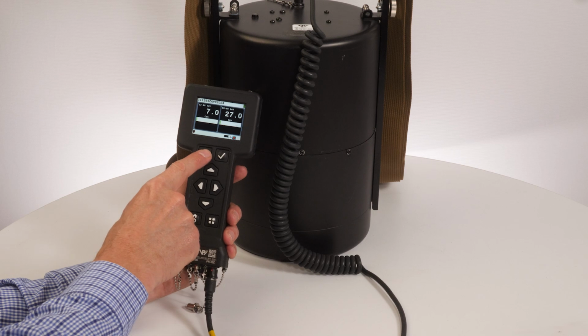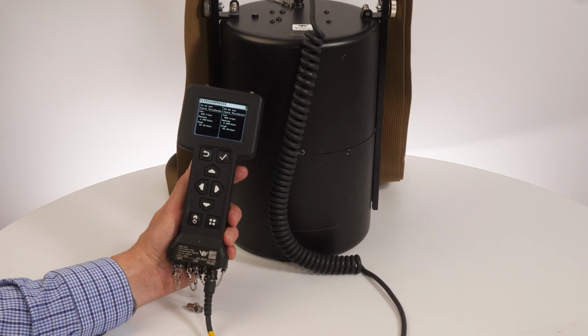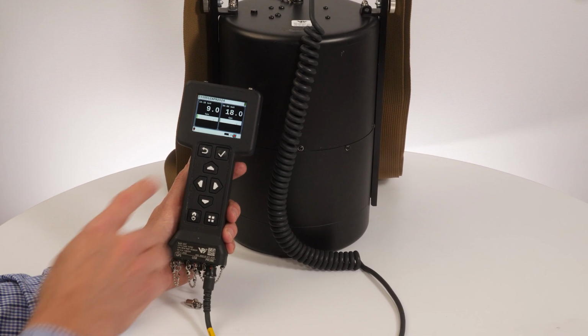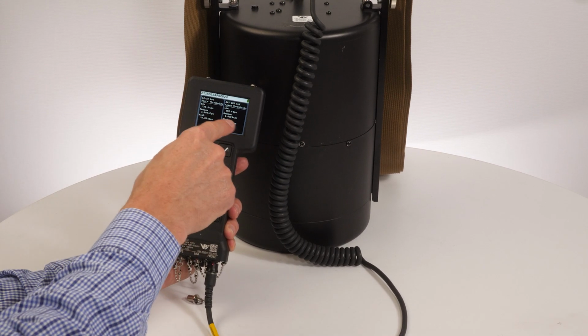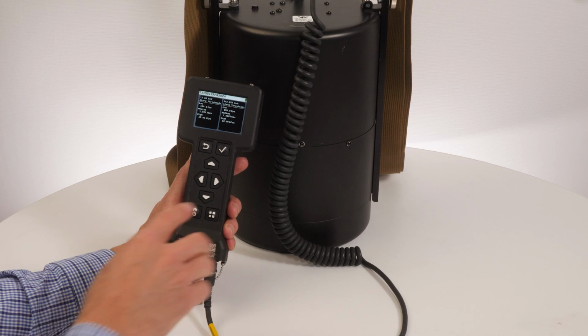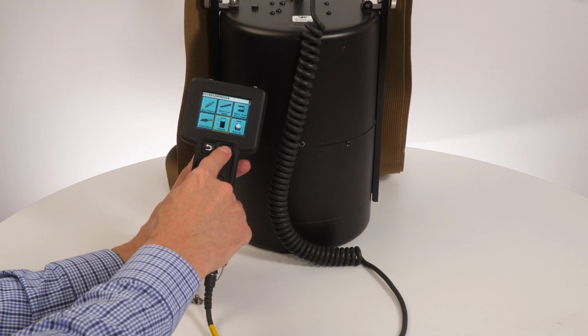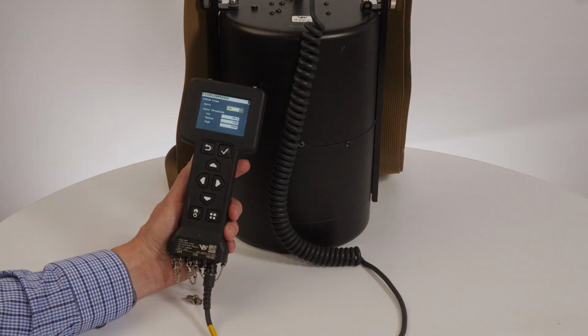While on the home screen, press the back key to display the alarm thresholds. Thresholds displayed will correspond to the current channels on the home screen. To see the others, toggle first using the Enter key, then press the back key again. If you need to change the alarm thresholds, you can go to the main menu, select Probe, choose the FIDLER probe, and go to the Advanced screen to make changes.